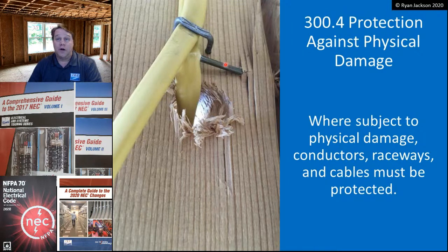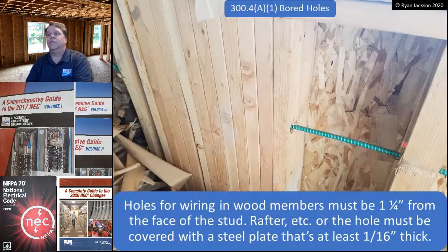Here's that cable, a nail that has pierced the jacket of the cable. And I want you to notice something too, if you can see it. That nail is not from drywall. That's not from the inside of the house. That's from the outside of the house. I can see oriented strand board, OSB. So that actually came from the outside, like the stucco guy or somebody hit it. Probably not stucco with 16-penny nails. But I want you to remember that the inch and a quarter rule that we're going to talk about applies from both sides of the framing member, from the inside and the drywall installer, and from the outside with the stucco installer. We get a lot of problems of stucco contractors hitting cables in my area.